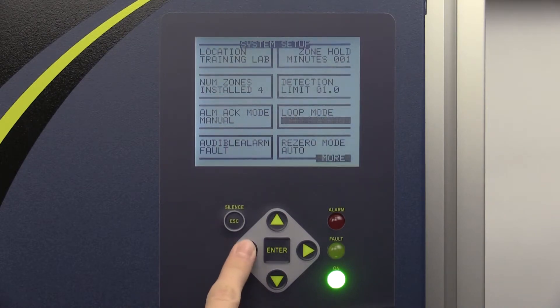In highest concentration mode, the device adjusts the two current outputs to correspond to the zone number with the highest PPM reading and the value of that PPM reading, respectively. These outputs will remain corresponding to whichever zone has the highest PPM concentration reading.